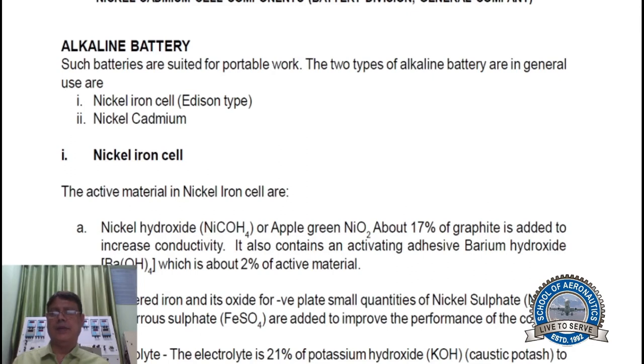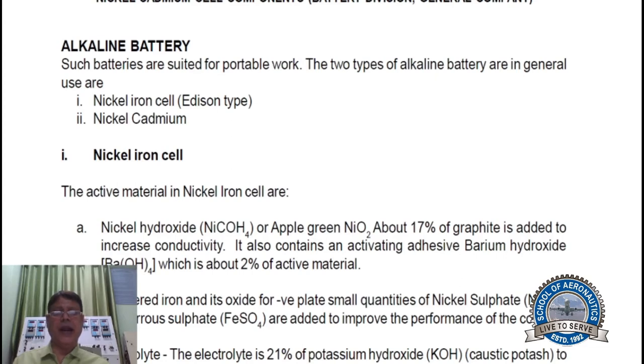Nickel Iron cell. The active materials in a nickel iron cell are: nickel hydroxide or nickel oxide, NiO2, for the positive plate. About 17% of graphite is added to increase conductivity. It also contains an activating additive, barium hydroxide, which is about 2% of active material.